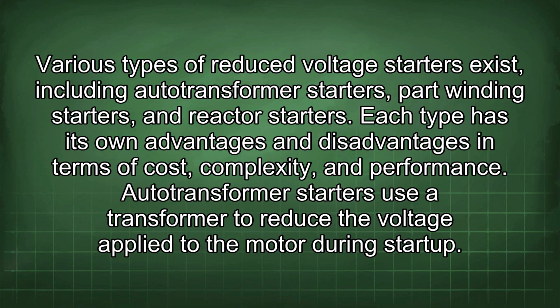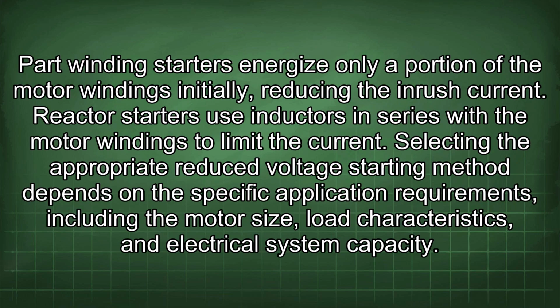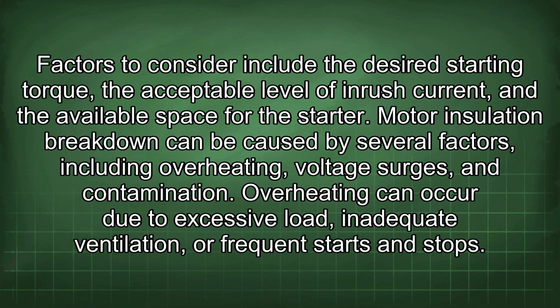Auto-transformer starters use a transformer to reduce the voltage applied to the motor during startup. Part-winding starters energize only a portion of the motor windings initially, reducing the inrush current. Reactor starters use inductors in series with the motor windings to limit the current. Selecting the appropriate reduced voltage starting method depends on the specific application requirements, including the motor size, load characteristics, and electrical system capacity. Factors to consider include the desired starting torque, the acceptable level of inrush current, and the available space for the starter.